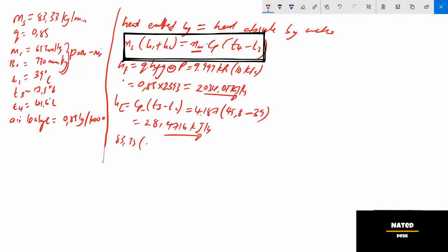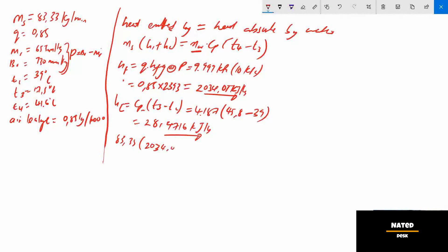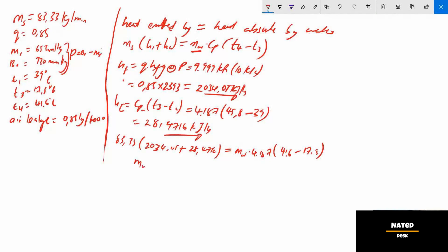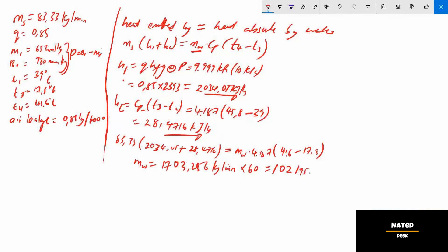Now substituting all values into the heat balance equation: ms with h1 and hc calculated, equals mw × 4.187 × (t4 − t3). Solving for mw gives 1703.256 kg per minute. Since the answer is required in kg per hour, we multiply by 60, giving a final answer of 102,195.37 kg per hour.